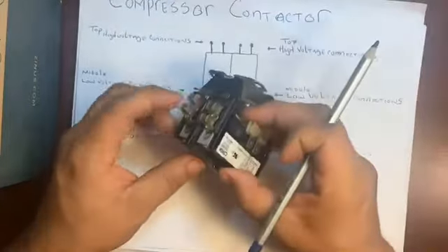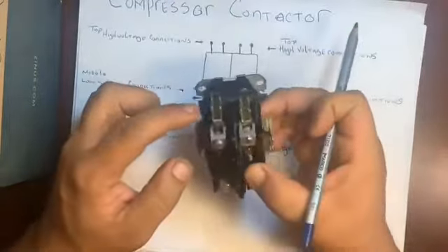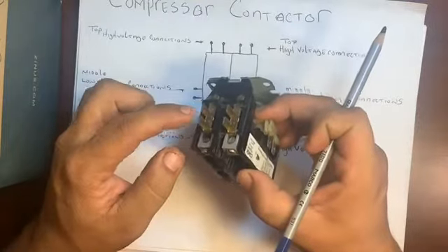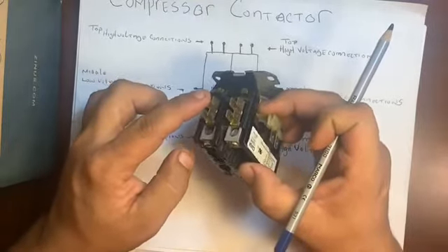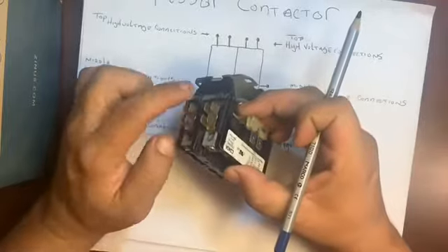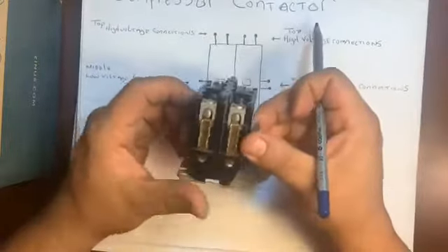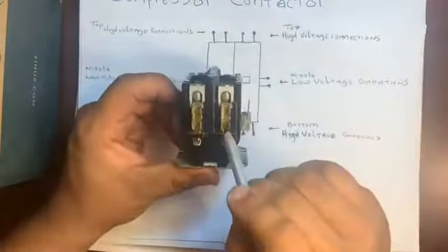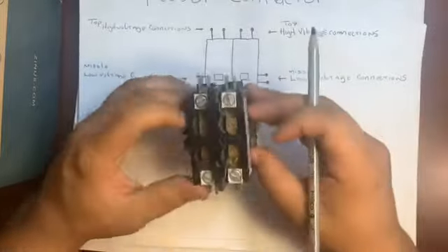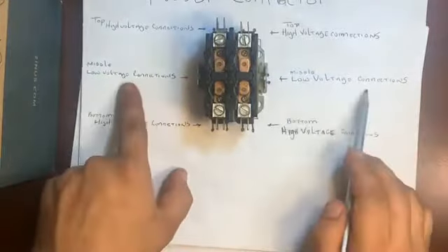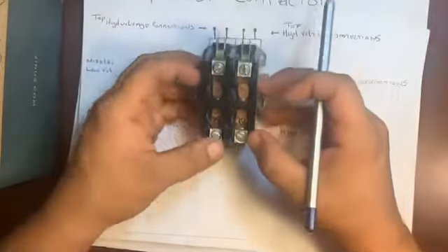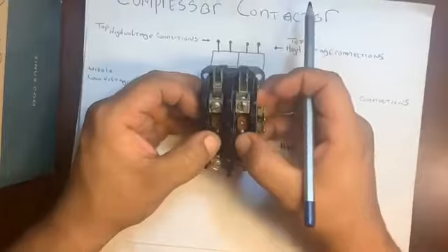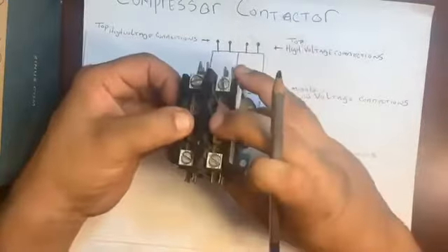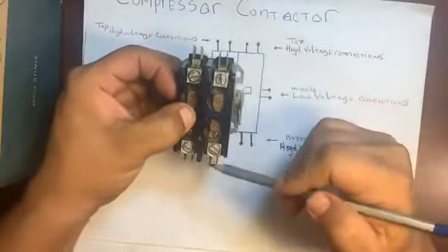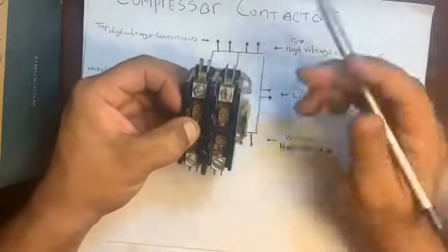The reason we have multiple plugs like this is because in the condenser, we're gonna have a fan that needs this leg of power, a compressor that needs this leg of power. Sometimes there's other things in higher end systems that'll need more legs. But that's why we have multiple legs. And as you see, if you connect one to this leg, it's gonna be connected because these metals go all the way through. So when low voltage is applied to the sides, middle, low voltage connections, there's a plunger that falls down. This falls down, this plunges down and makes contact and then continues the circuit so the voltage can flow through.